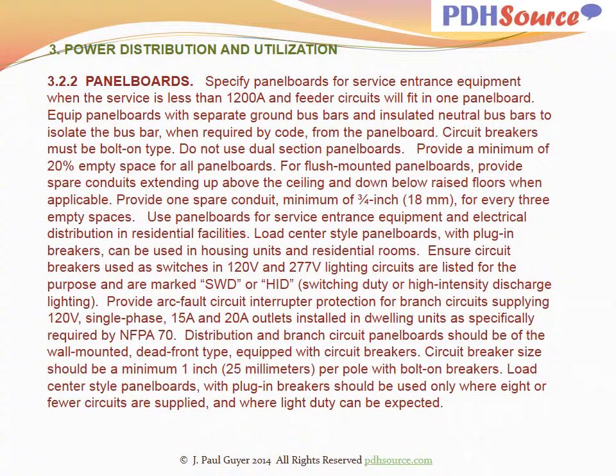For flush-mounted panel boards, provide spare conduits extending up above the ceiling and down below raised floors when applicable. Provide one spare conduit, minimum of 3/4 inch, for every 3 empty spaces. Use panel boards for service entrance equipment and electrical distribution in residential facilities. Load center style panel boards with plug-in breakers can be used in housing units and residential rooms. Ensure circuit breakers used as switches in 120 volt and 277 volt lighting circuits are listed for the purpose and are marked SWD or HID, switching duty or high intensity discharge lighting.